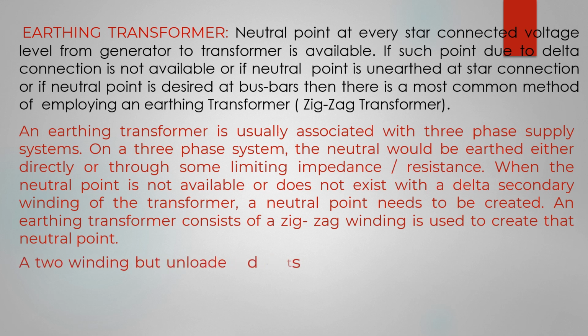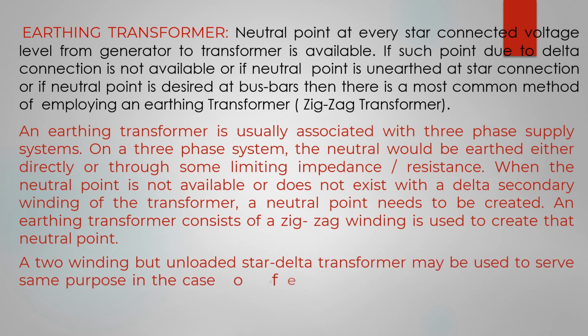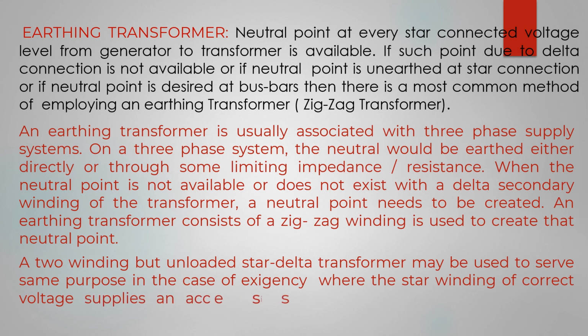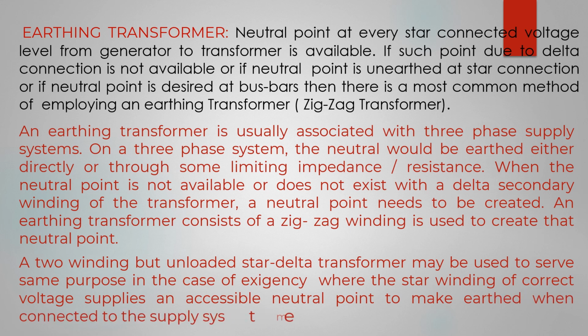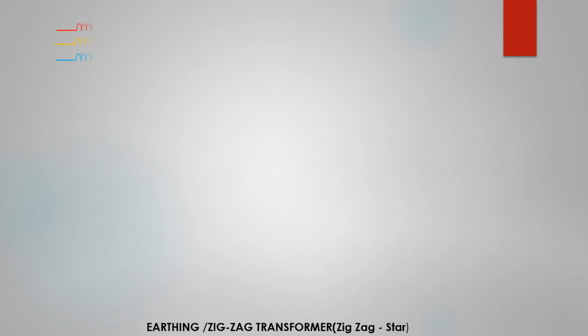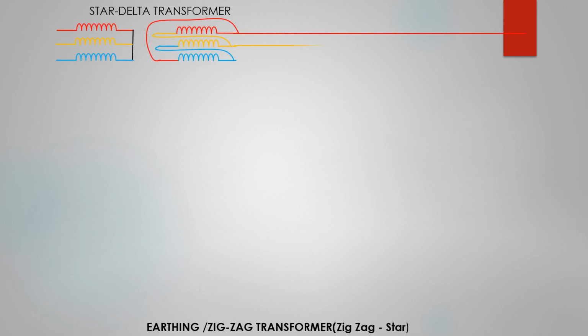A two-winding but unloaded star-delta transformer may be used to serve the same purpose in case of exigency, where the star winding of correct voltage supplies an accessible neutral point to make earth when connected to the supply system. This is a star-delta transformer. As usual, the delta side has no neutral point, so there is no return neutral path for earth fault currents to flow.